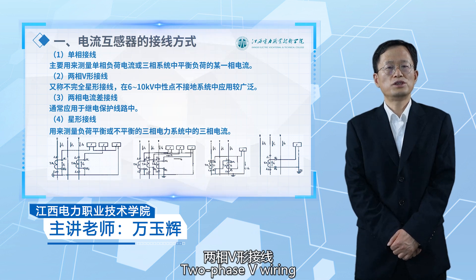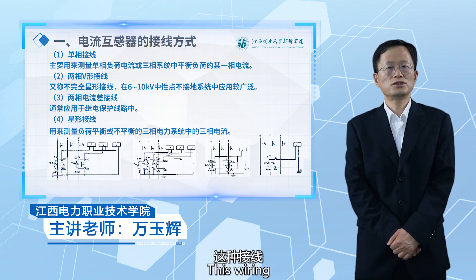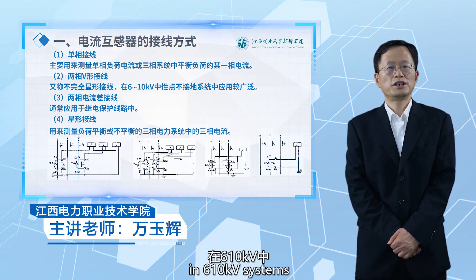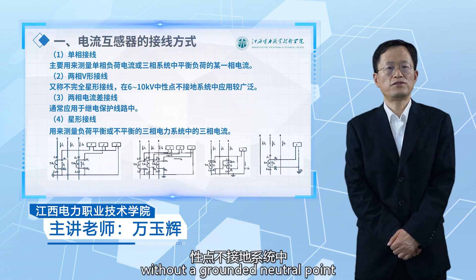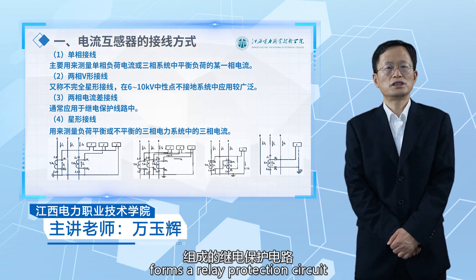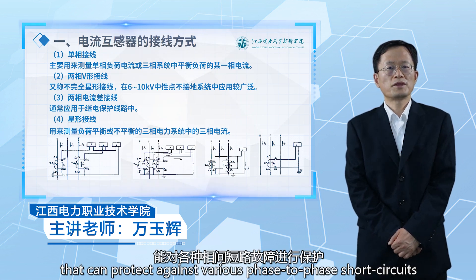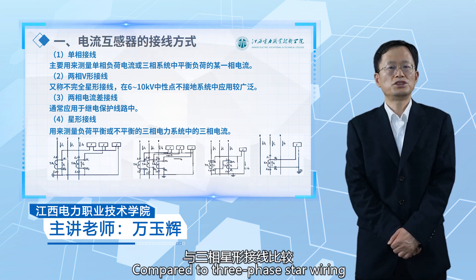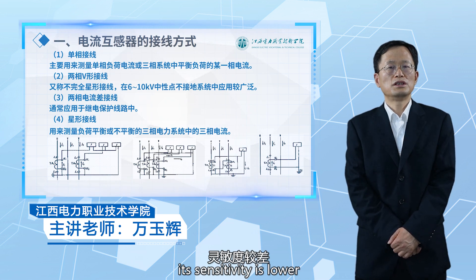The second is two-phase V wiring, also known as incomplete star wiring. In 6–10 kV systems without a grounded neutral point, it is widely used. The incomplete star wiring method forms a relay protection circuit that can protect against various phase-to-phase short circuits, but sensitivity varies with different fault types. Compared to three-phase star wiring, its sensitivity is lower.